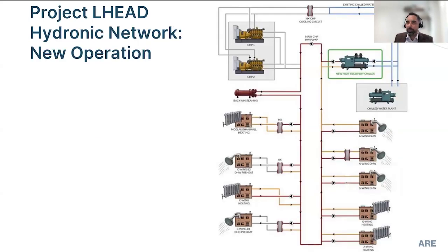So maybe you can walk us through the hydronic networks. What were the challenges you guys faced with the existing systems, or were they actually set up in a way that you could easily tie in your heat recovery chiller? Yeah, so the system at Lake Ridge, coming into an existing facility, Lake Ridge has plenty of cooling installed. They had 4,000 tons of existing chillers, typical centrifugal chillers, and those chillers operate in the shoulder and summer seasons. And in the winter, they actually run a free cooling heat rejection system, so circulating chilled water through the hospital, rejecting that heat to the outdoors without needing to run a chiller.